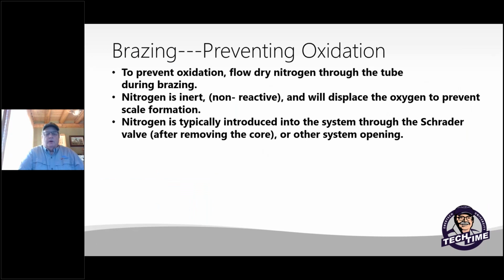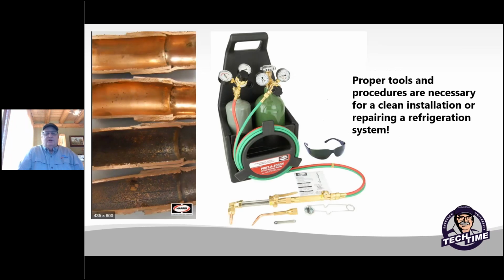When you're brazing, we're going to make sure you prevent oxidation in the system. That's why the new refrigerants really recommend going with a nitrogen purge while you're brazing. It displaces the oxygen and helps prevent any scale forming. So my next slide, I'm going to show you what it looks like inside if you don't use nitrogen. As you can see on the slide, it's pretty well black inside there where you didn't have any nitrogen flowing.